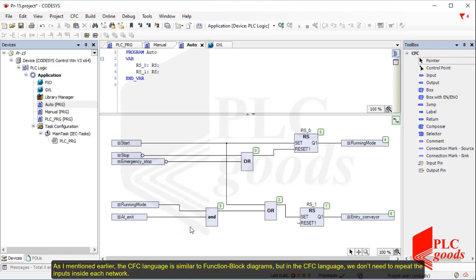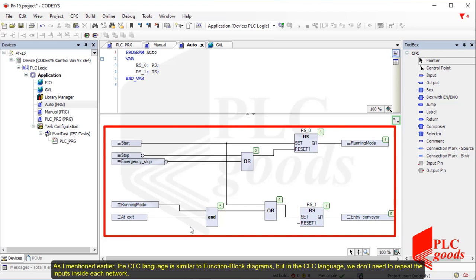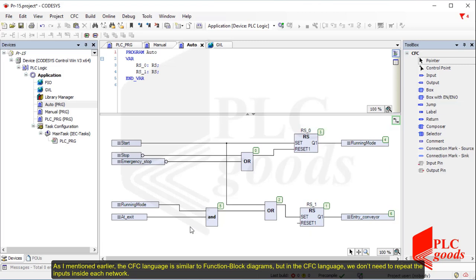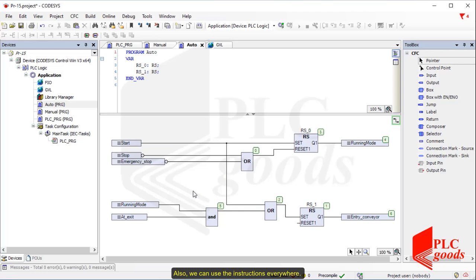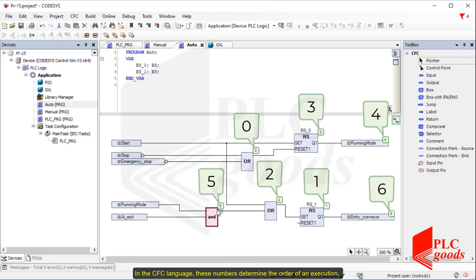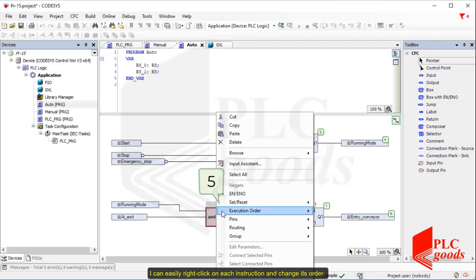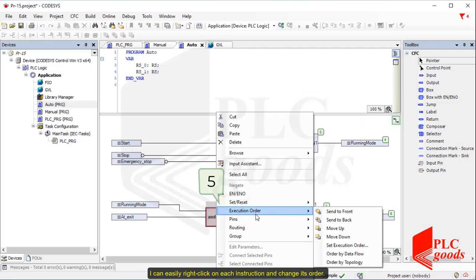As I mentioned earlier, the CFC language is similar to function block diagrams, but in the CFC language we don't need to repeat the inputs inside each network. I can easily get a branch of any input and connect it to the inputs of other instructions. Also, we can use the instructions everywhere. In the CFC language, these numbers determine the order of execution. I can easily right-click on each instruction and change its order.